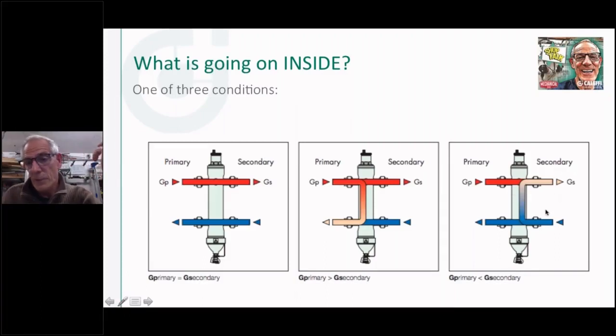So again, getting to our last picture here. Now, obviously what we're showing here is if we've got more flow on this side than on this side, you can see where the temperature blending is going out here. That's where the blending point is with this condition. So you can see the different conditions: flow rate the same, less than, more than on one side or the other. And again, you want to know that because if you're expecting a certain output temperature, you've got to make sure that the temperature coming in, the temperature returning, and the flow rate going through it are going to give you that temperature.